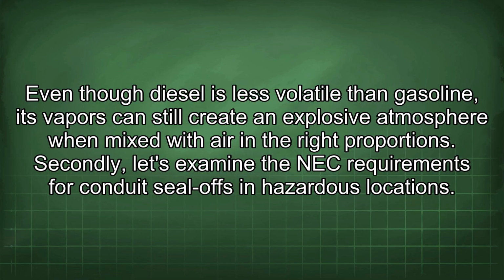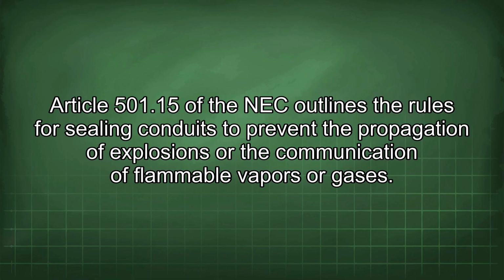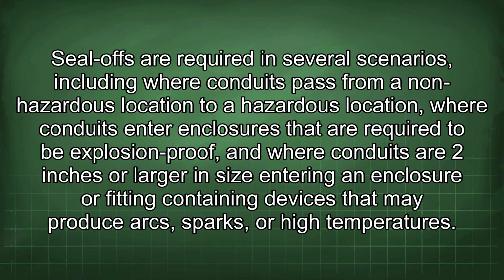in the right proportions. Secondly, let's examine the NEC requirements for conduit seal-offs in hazardous locations. Article 501.15 of the NEC outlines the rules for sealing conduits to prevent the propagation of explosions or the communication of flammable vapors or gases. Seal-offs are required in several scenarios, including where conduits pass from a non-hazardous location to a hazardous location, where conduits enter enclosures that are required to be explosion-proof, and where conduits 2 inches or larger in size enter an enclosure or fitting containing devices that may produce arcs, sparks, or high temperatures.